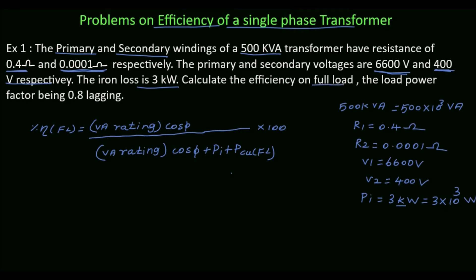We have to calculate the full load efficiency, the load power factor being 0.8 lagging, so cos φ is 0.8. The full load percentage efficiency formula is: VA rating × cos φ, divided by VA rating × cos φ plus iron loss plus full load copper loss. The VA rating, cos φ, and iron loss are all given. The only unknown parameter is the full load copper loss.